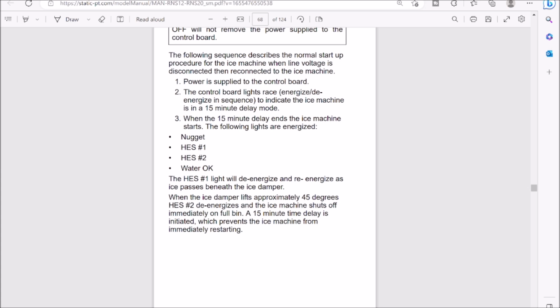The issue with this unit is every time we lock out, there's a 15-minute delay. Okay, this is an issue because just say I want to test 4 components, it's going to take me 1 hour because I'm going to keep locking myself out. Okay, so because of that, we're going to have to troubleshoot strategically so that I'm not going to test 4 components. I don't want to waste an hour waiting around with these 15-minute delays.